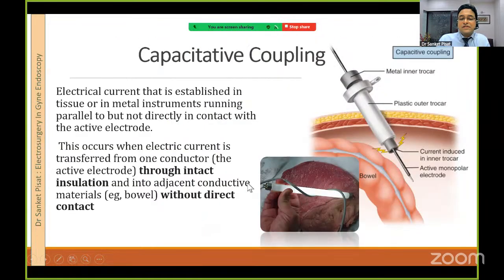The simplest example of this is something you can see they sometimes demonstrate when they demonstrate electrosurgical equipment. If you wind a wire around a tube light, the tube light is not connected anywhere to any source, and you switch on the pedal or you activate the current, just the fact that the wire is wound around the tube light is enough to make the tube light glow, because the current activates the tube light without physically touching or leaking onto the tube light itself. So the point is capacitive coupling happens when current passes through or in the center of another conductor, activating that conductor and causing damage to the organ which is in contact with that secondary conductor. So I hope this is clear.